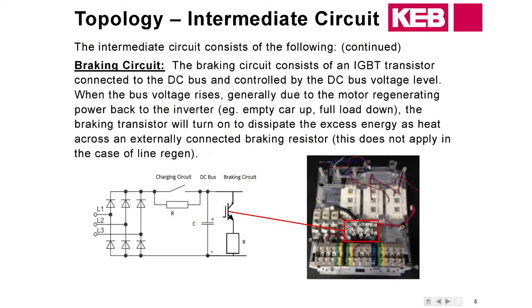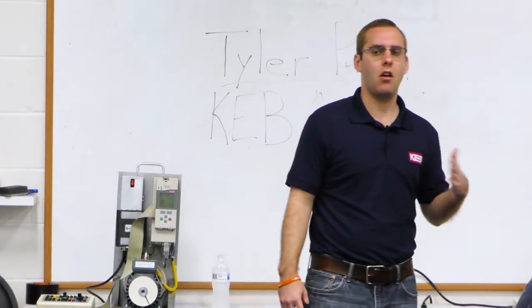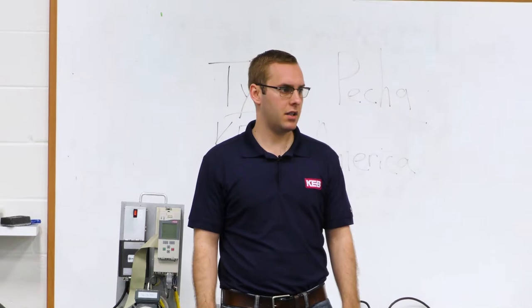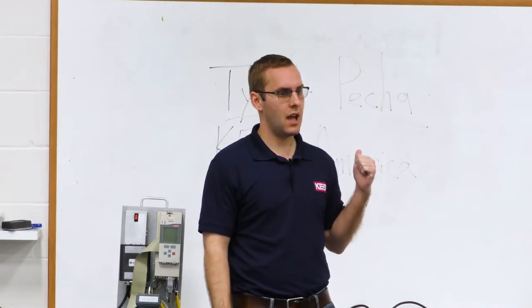Continuing on with the intermediate circuit, we feature our braking circuit internal to the drive. The braking circuit contains the braking transistor, which turns on and off when your DC bus rises to a certain level. Some drives feature the transistor on the outside, but ours is on the inside to help create a more compact footprint. If you're using a braking resistor to dissipate excess DC bus voltage, this transistor turns on and off to dump that extra voltage across the resistor. If you are using a regen, this will not be active.